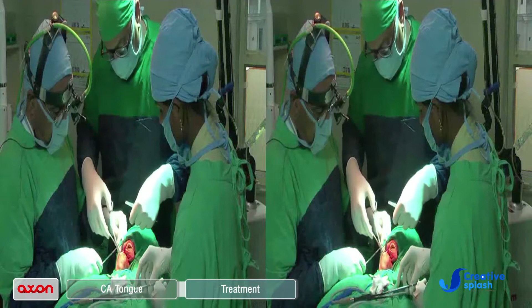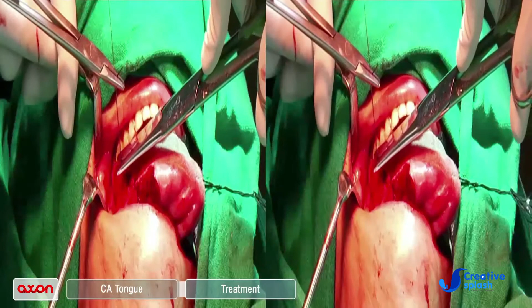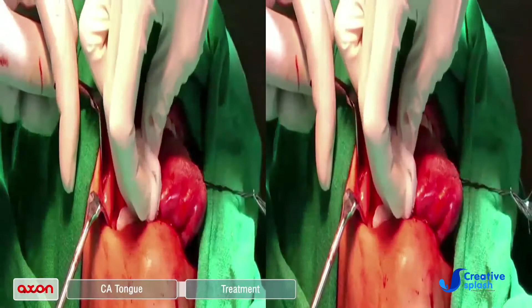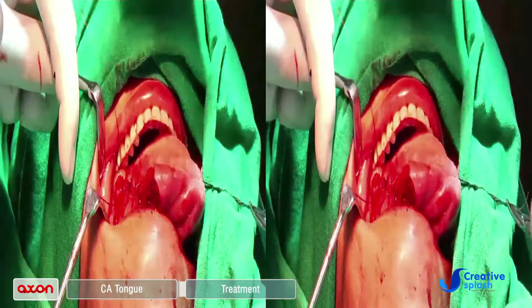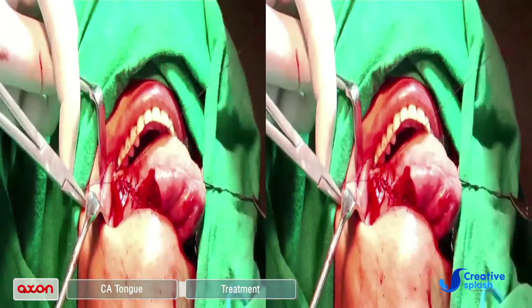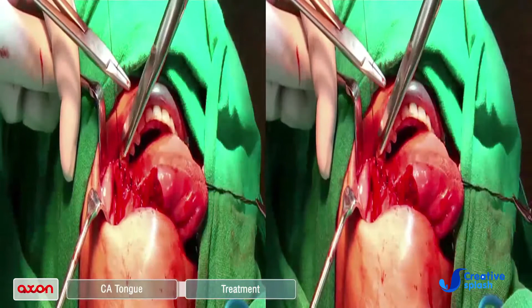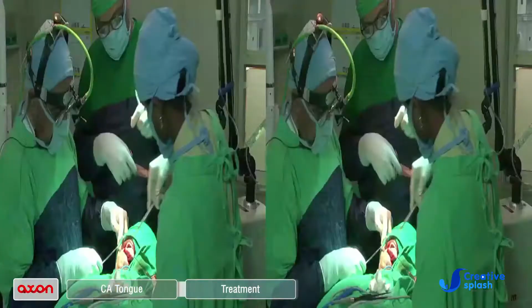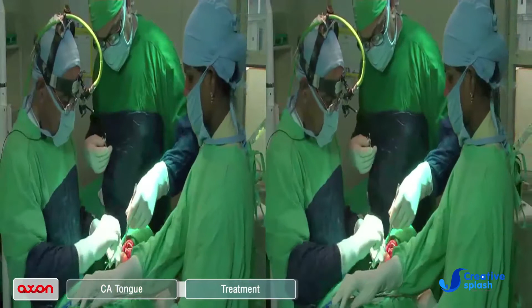In earlier days, when lasers were not in practice, this was removed probably by either a straightforward cold surgical instrument like a knife, or maybe a diathermy, which is an extremely heat producing instrument. And the lateral thermal damage of the diathermy cautery is almost 1.5 centimeters. So you imagine that the patient will be subjected to tissue damage about 1.5 centimeters beyond what your eyes can see. And that is not desirable. Whereas the laser only heats up about 2 cells deep. That is less than 0.2 millimeters. That means there is negligible, about 10 microns. So there is very little lateral thermal damage.